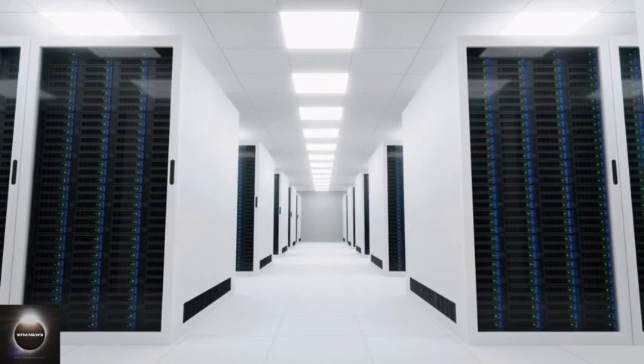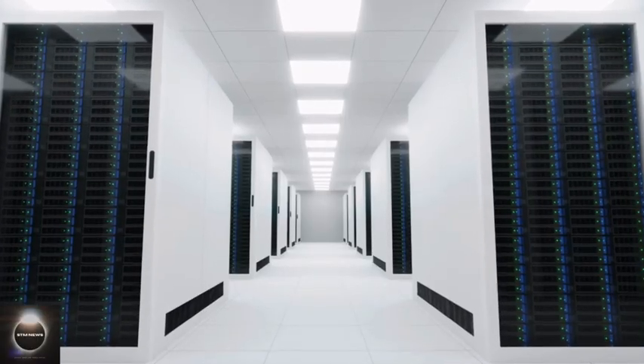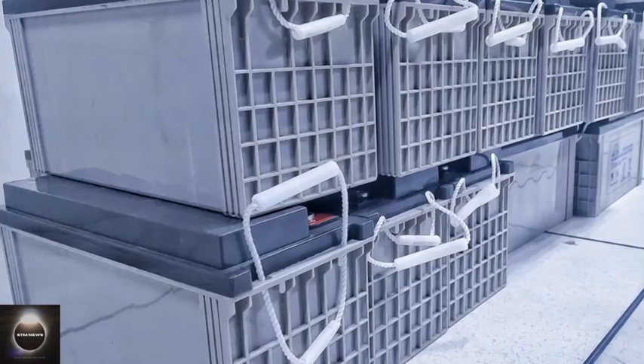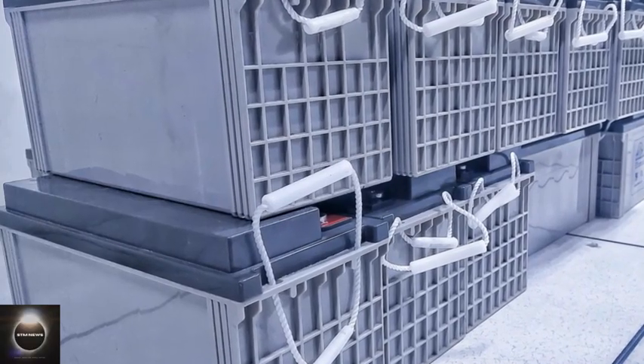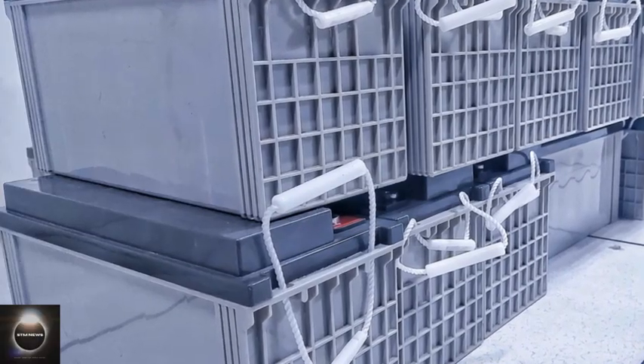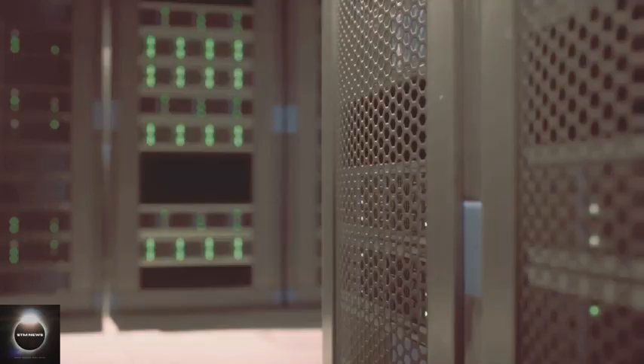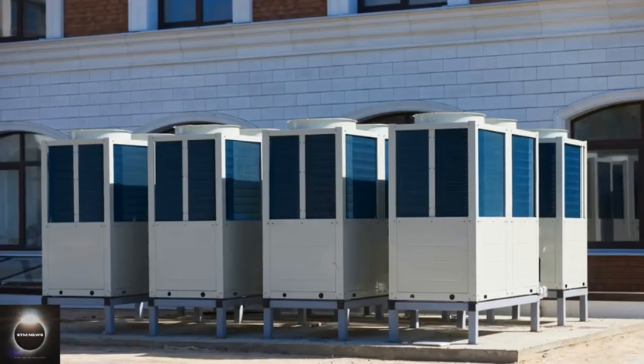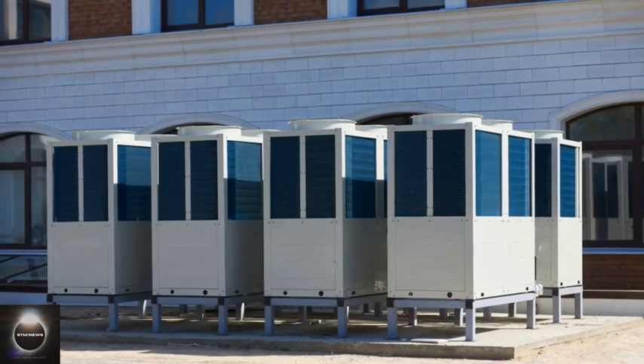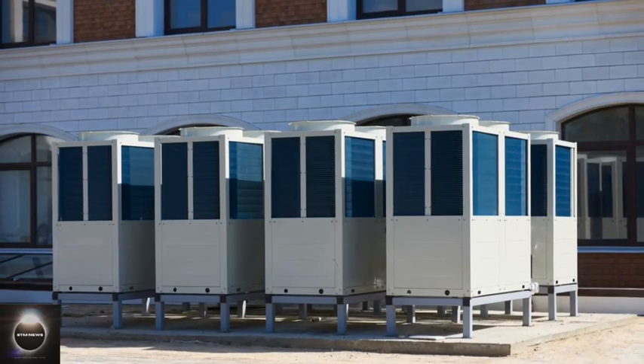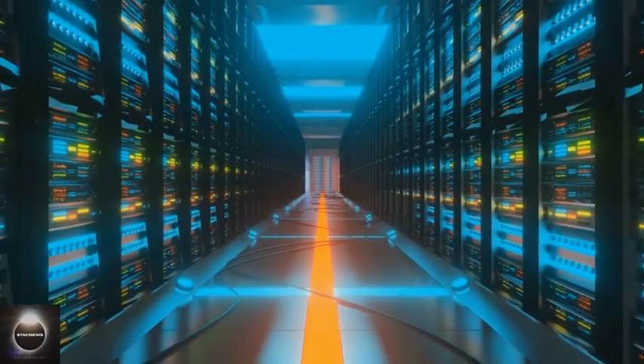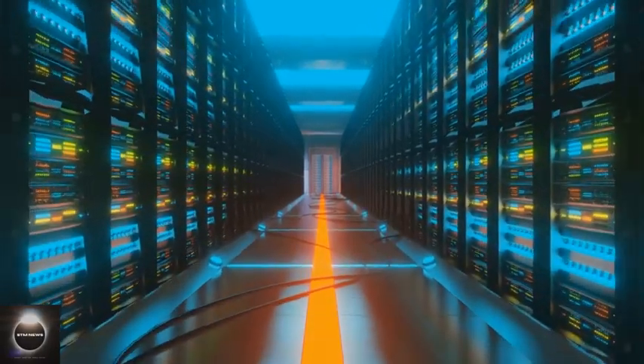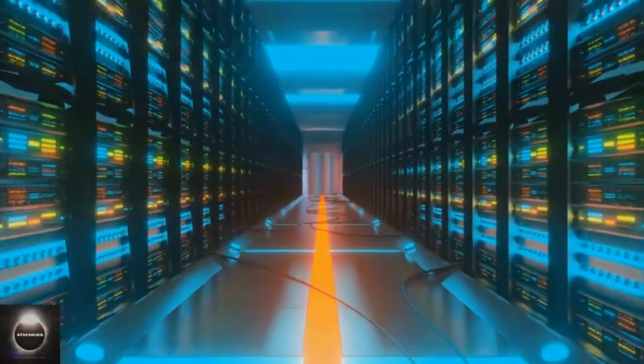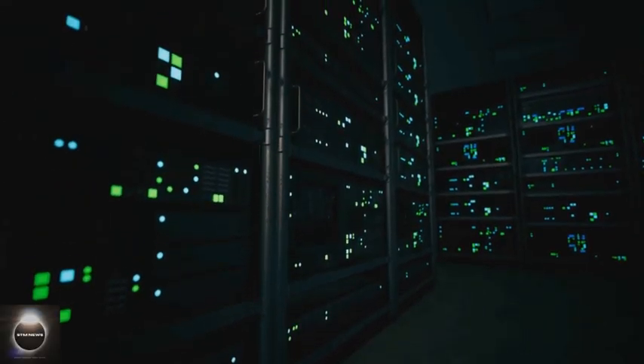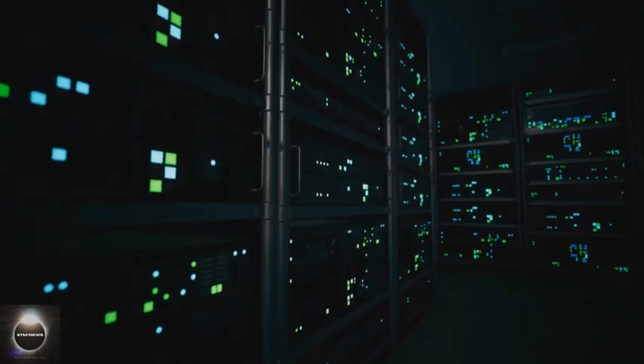Flooding a room with cold air is wasteful. Airflow must be managed. Arrange racks front to front for cold aisles and back to back for hot aisles. This basic layout prevents hot exhaust from contaminating cold intakes. CRAHs pressurize a plenum, delivering cool air up through perforated tiles at cold aisles. Servers draw that air through hot components and exhaust it into hot aisles. Cooling units reclaim hot air and repeat, efficient and predictable.